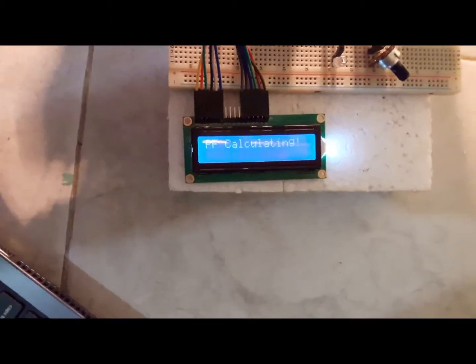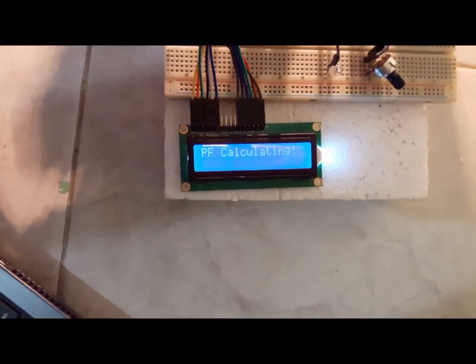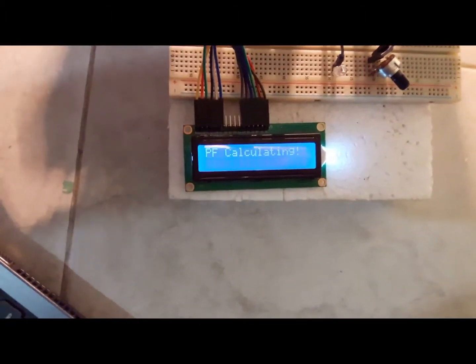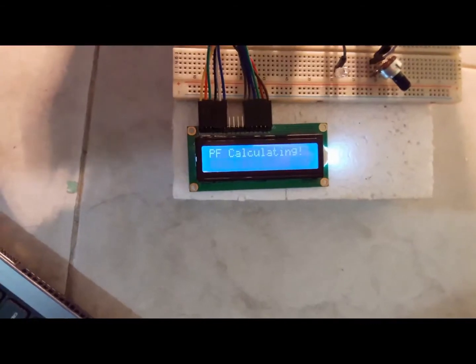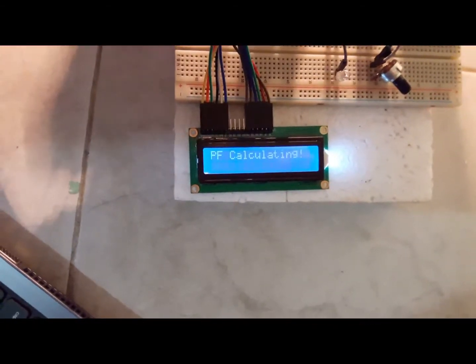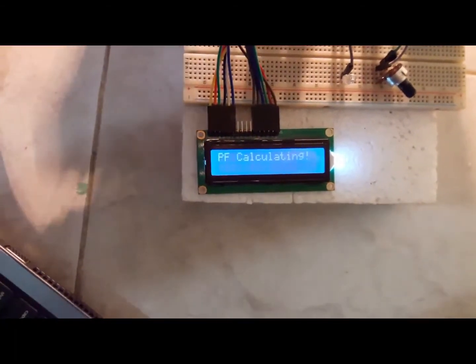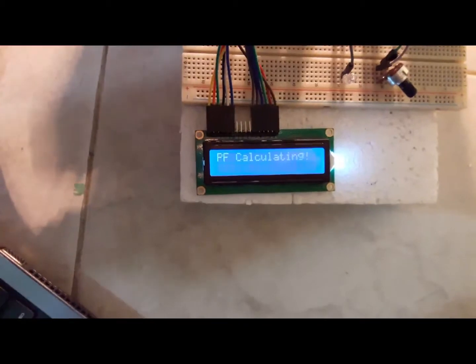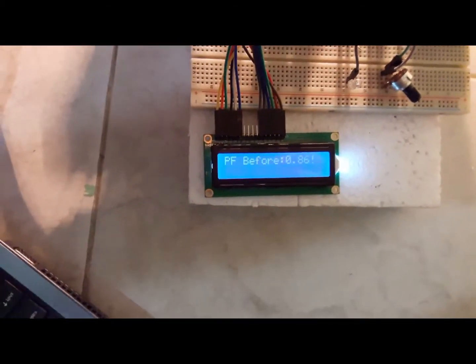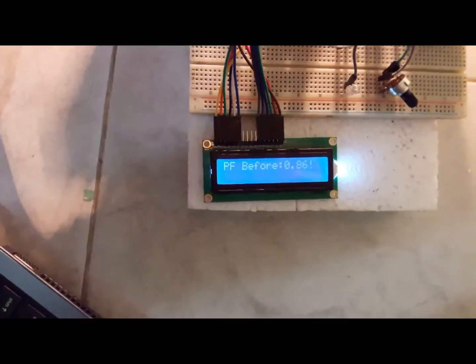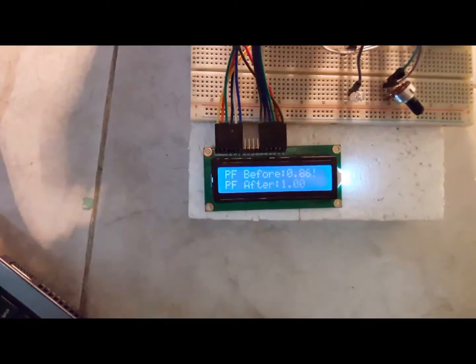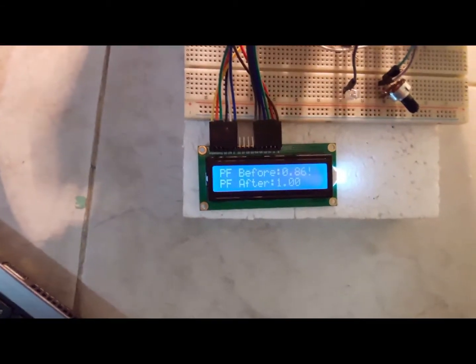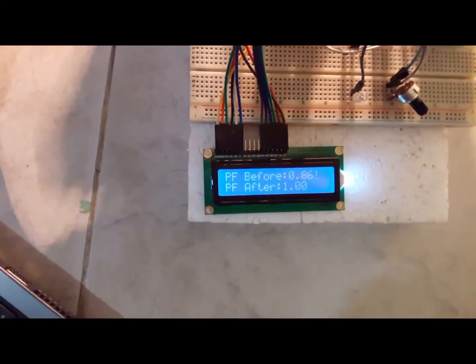Now it is calculating. It will take some time. Okay, this is the PF. Before improving it was 0.86, and after it is 1.